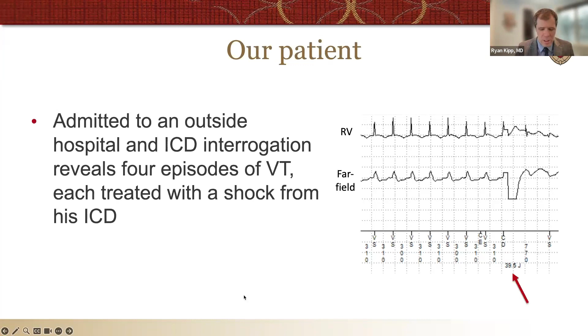This is a far field channel. This is what the heart rhythm looks like, kind of from a more superficial point of view, looking at the electrogram from the generator in the chest to the coil. And this helps the defibrillator determine if supraventricular tachycardia is occurring or if this is indeed ventricular tachycardia. By going through all of its algorithms, the device determined that this was indeed ventricular tachycardia. It charged the defibrillator, and then you can see here CE is charge enabled. It confirmed that the rhythm was still occurring and then delivered a 39.5 joule defibrillation, resulting in the rhythm being terminated.